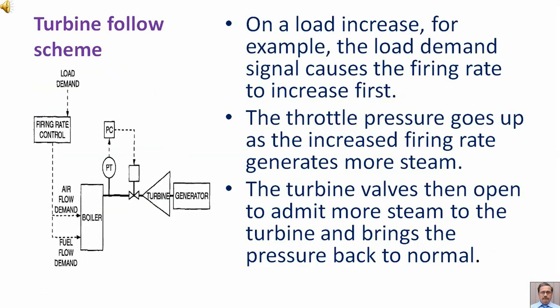On a load increase, for example, the load demand signal causes the firing rate to increase first. The throttle pressure goes up as the increased firing rate generates more steam. The turbine valves then open to admit more steam to the turbine and bring the pressure back to normal.